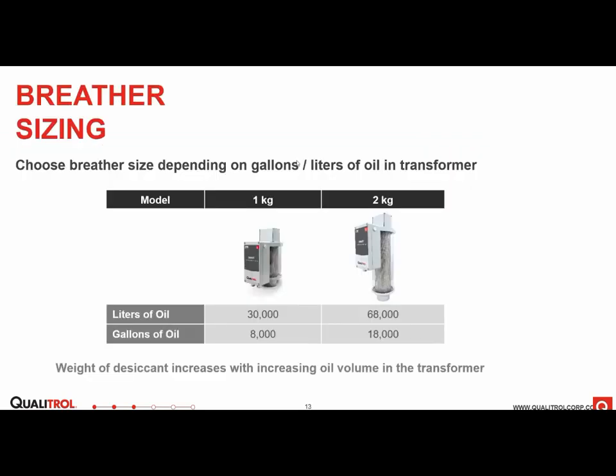So with our next generation of breather, we've updated so far our 1 kilogram and our 2 kilogram breathers. So our 1 kilogram breather is good for 30,000 liters of oil or 8,000 gallons. And the 2 kilogram breather is good for 68,000 liters of oil or 18,000 gallons. And these sizes are determined by the size of the transformer and the breathing cycles of transformers. So these are not exact numbers, but it's a good guideline to go by.